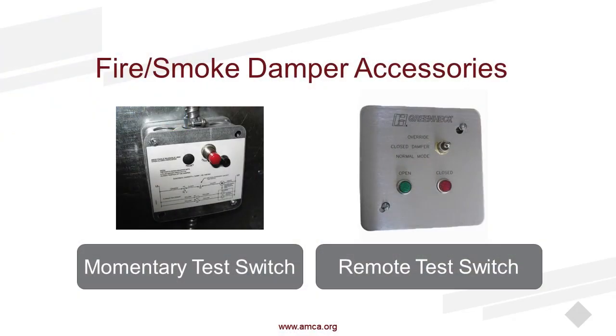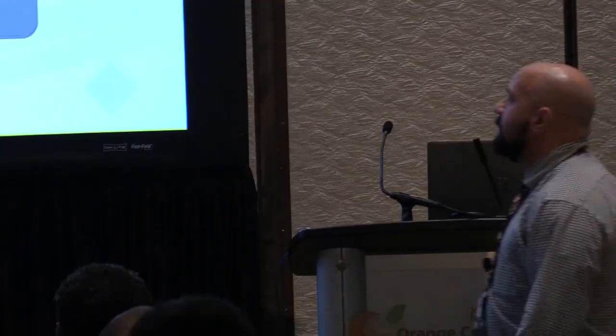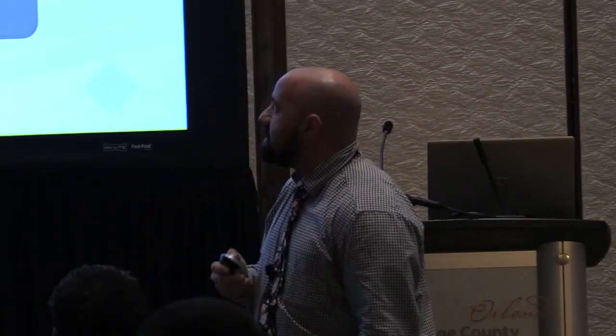That damper is physically closing. That's what we would call a visual inspection tool. I'm physically at the damper, looking at it open and close. Then I can wire in a remote test switch. I can have a damper way up there, and all I've got to do is walk up to it, push a button, and wait for those lights to change color. Green open, red closed. That satisfies the remote testing requirements of NFPA for your life cycle testing of the dampers.